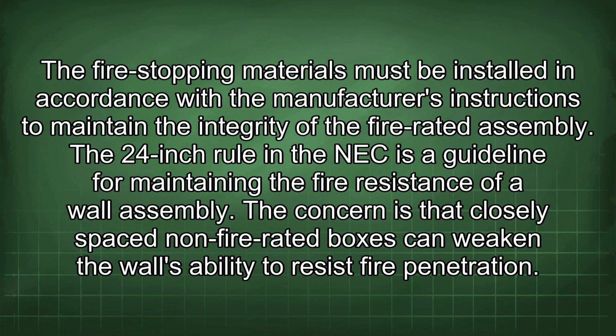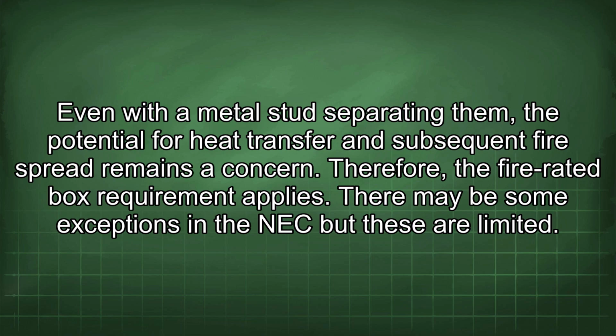The 24-inch rule in the NEC is a guideline for maintaining the fire resistance of a wall assembly. The concern is that closely spaced non-fire-rated boxes can weaken the wall's ability to resist fire penetration. Even with a metal stud separating them, the potential for heat transfer and subsequent fire spread remains a concern. Therefore, the fire-rated box requirement applies. There may be some exceptions in the NEC, but these are limited.